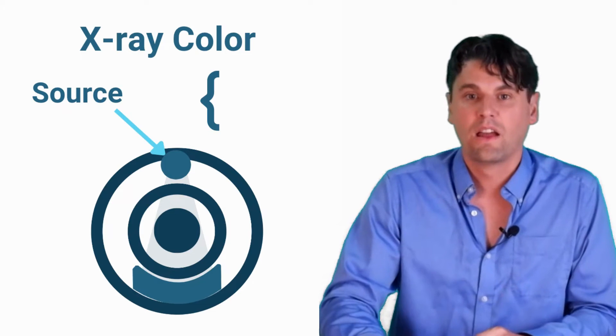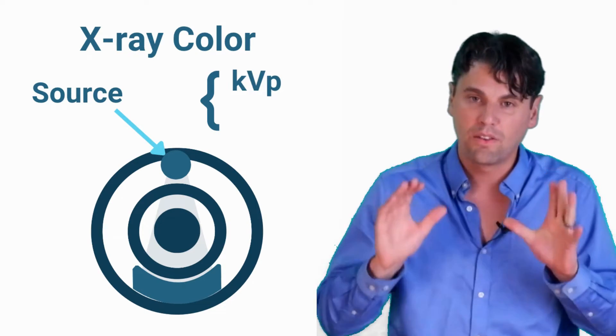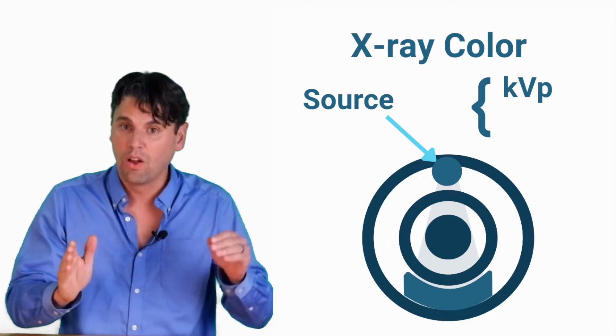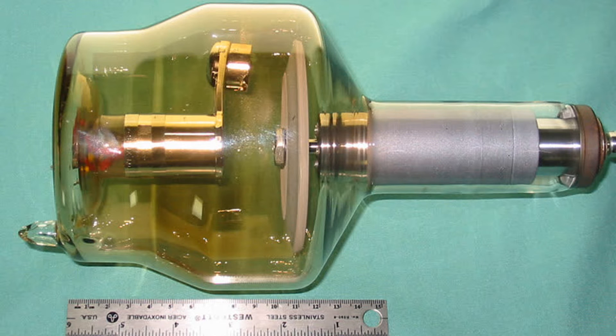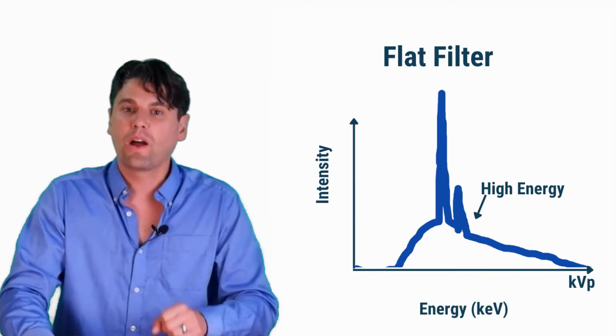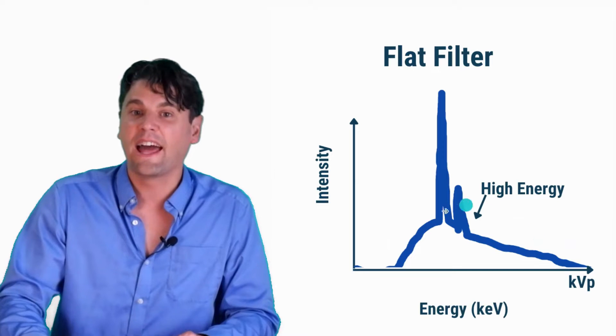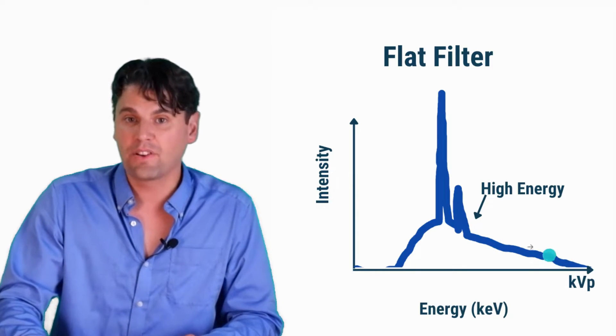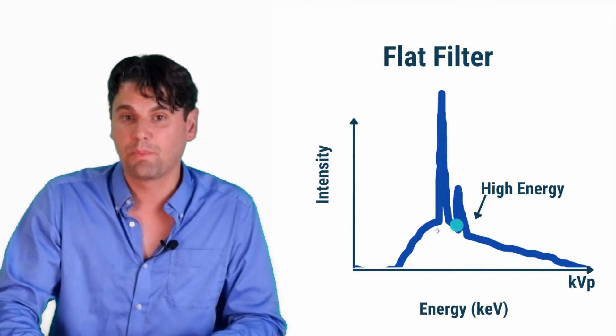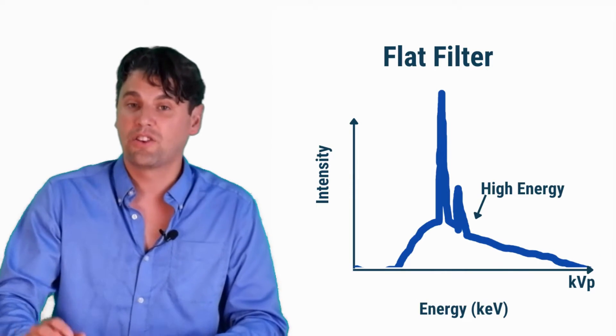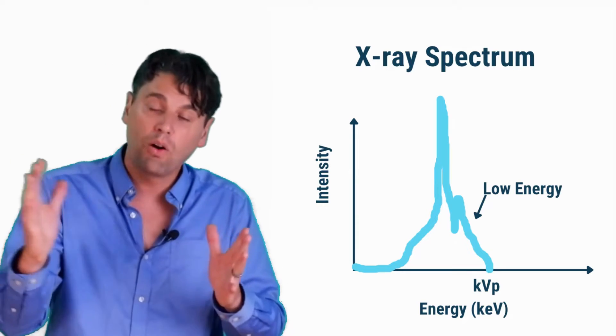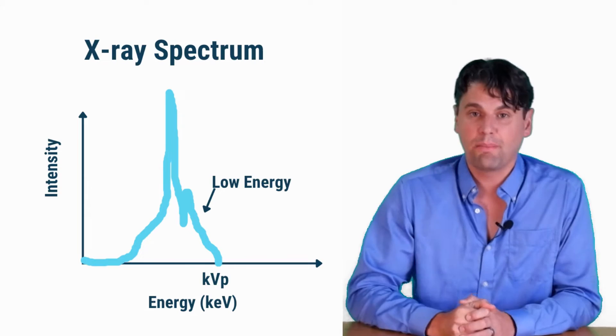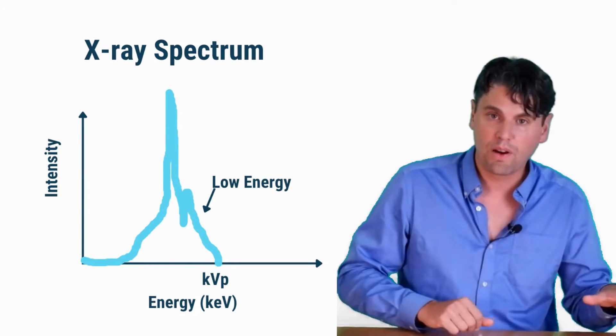On the source side, you can change the KVP — the knob which controls the potential from the electrons getting accelerated before they bang into the anode and the x-rays are generated. A standard spectrum at a higher KVP has a certain average energy. You can then change to a lower KVP and by doing so you make different measurements for the lower KVP and the higher KVP. The Hounsfield unit value will change when you go from a higher to a lower KVP, and that same information is used in dual energy imaging.